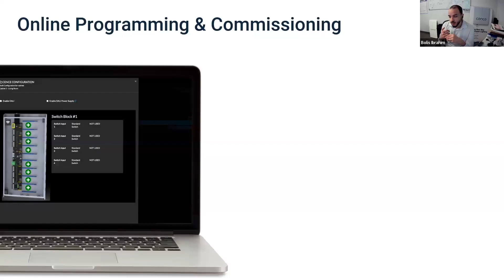So setting the milliamps: in constant current, you put a milliamp set point, right? And then in constant voltage, you put a milliamp tripping point. So a point at which you want the circuit to act like a breaker and shut off when it passes a certain milliamps. These systems typically you'll find not more than 4,000 milliamps or 4 amps. So 24 volts times 4 amps is going to give you roughly 100 watts. And that's what we do there. Every manufacturer has interesting software for management these days.